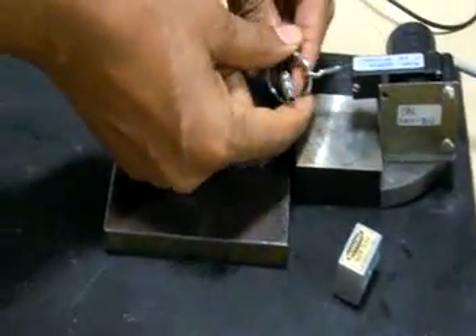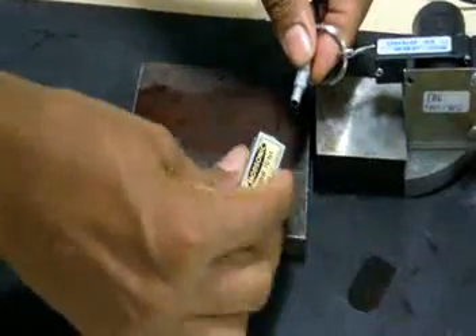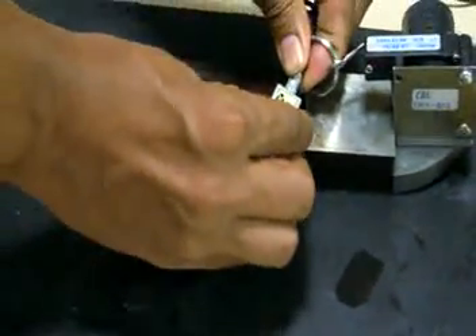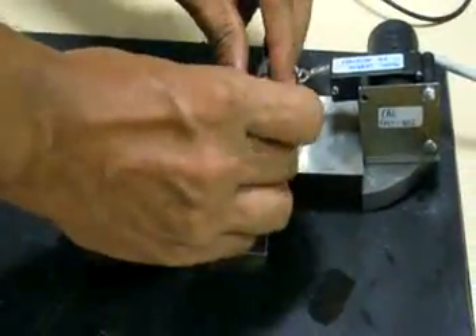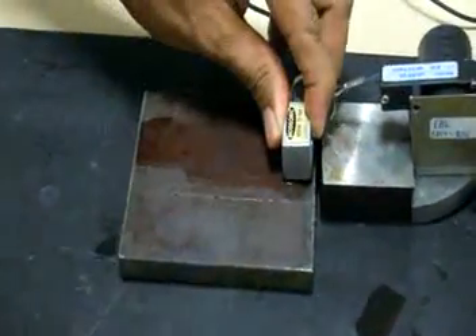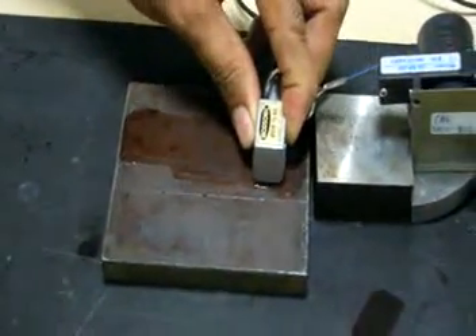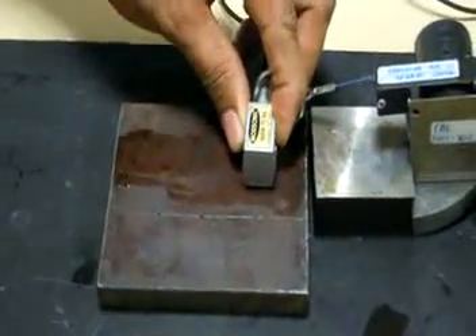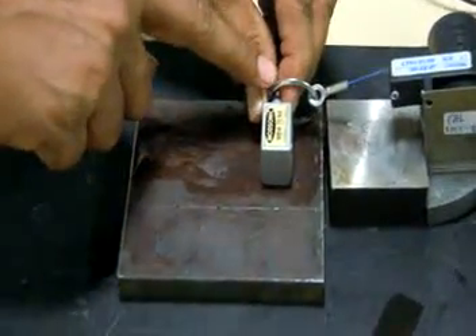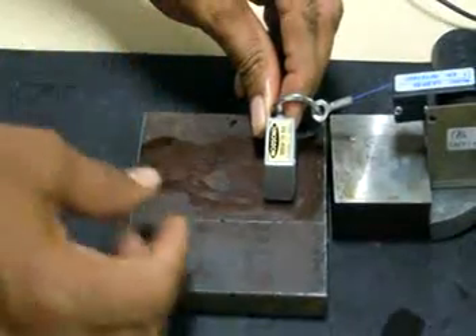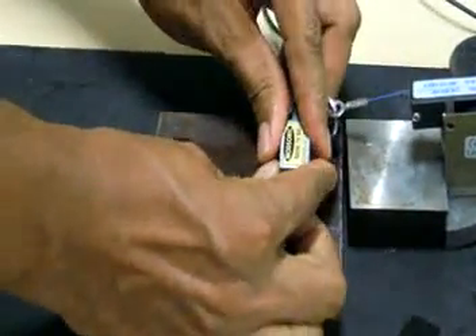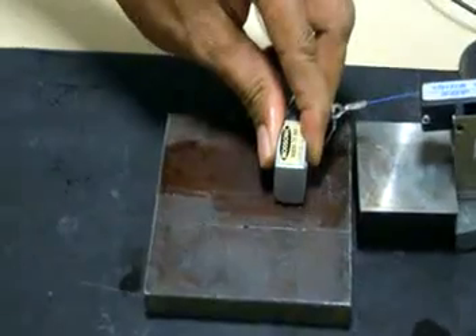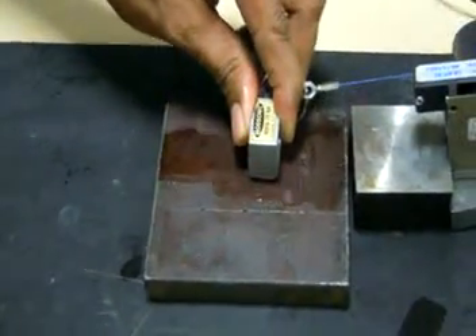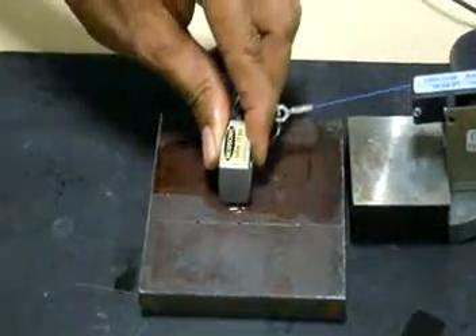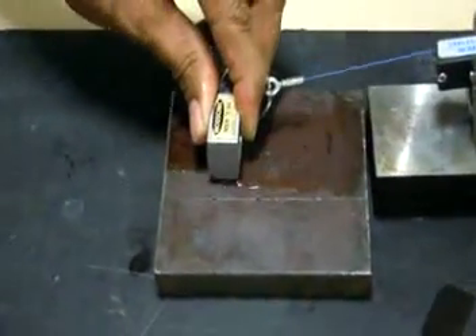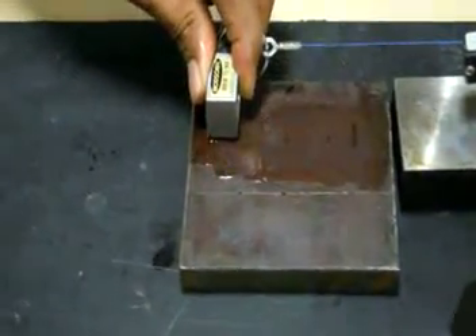Yeah, in a similar way we can also do the inspection using the angle probe, and any weld examination with raster scanning is possible to perform. As you can see, the ring at the end of the string has been slipped onto the probe. It is attached to the probe, and then the raster scanning is performed. So it is possible then to generate the same data as we have earlier seen using a single crystal normal probe.